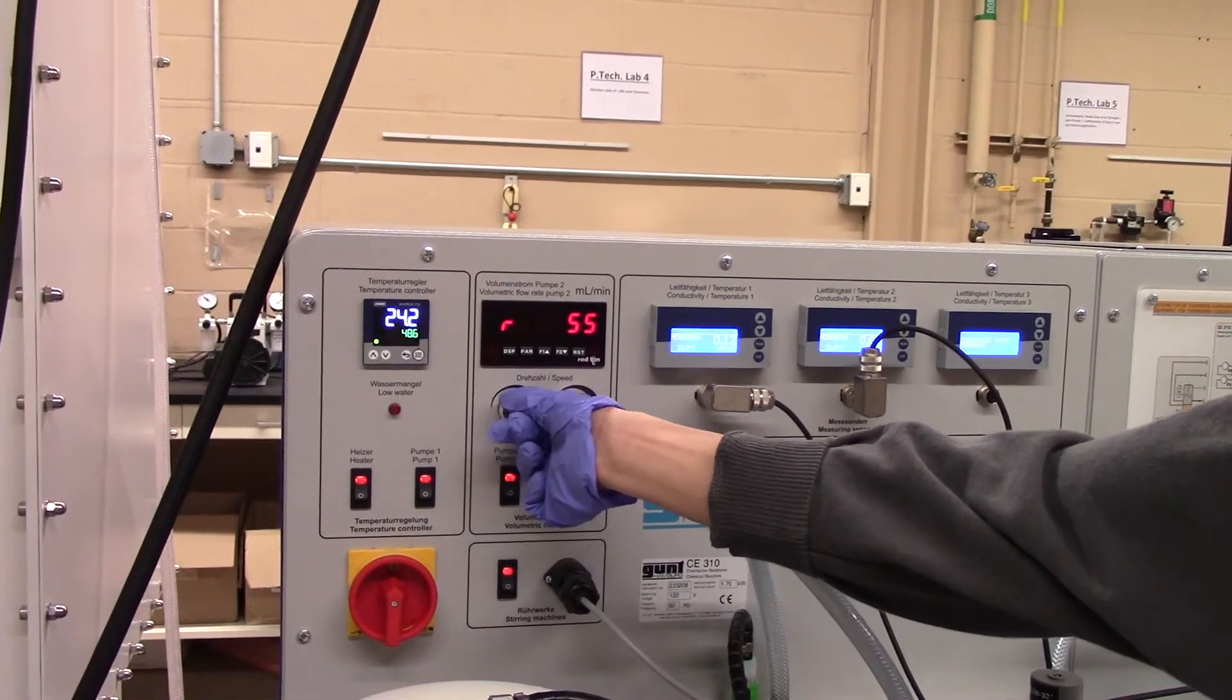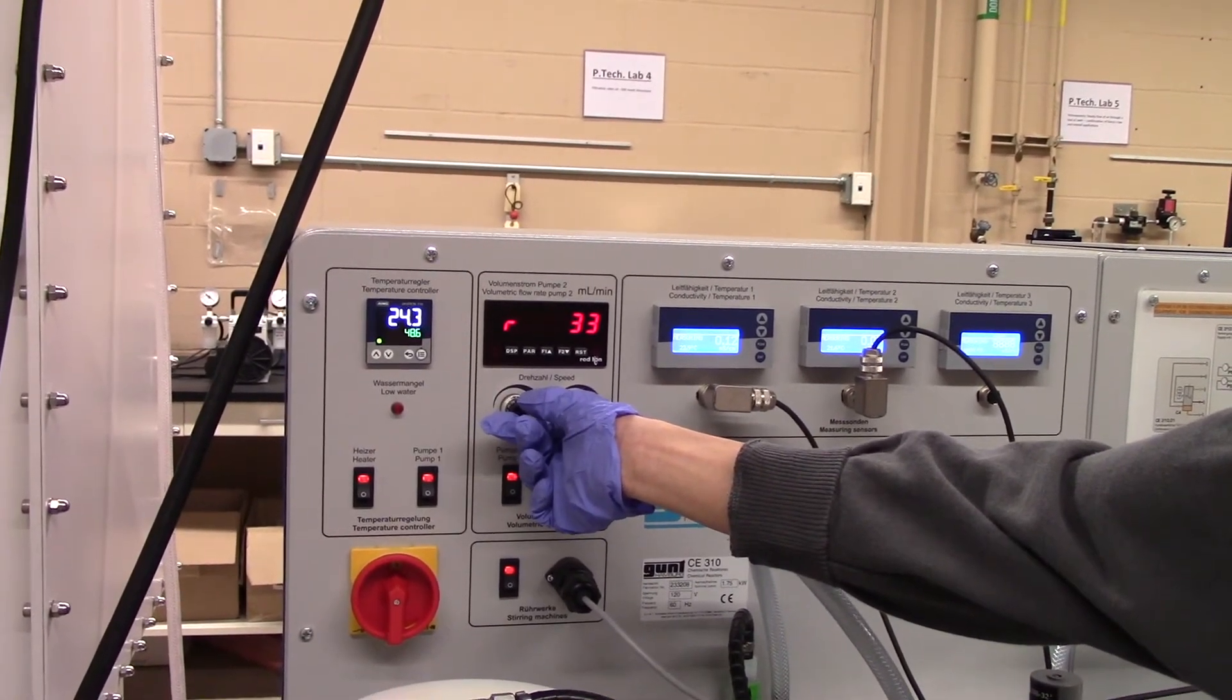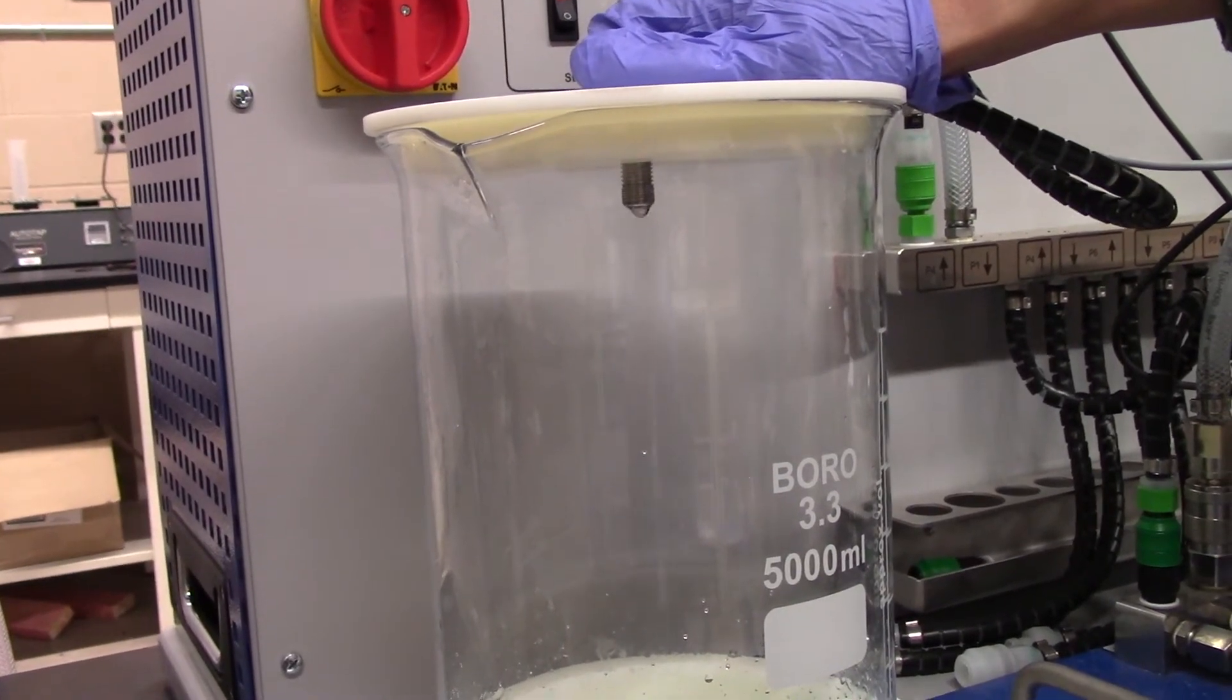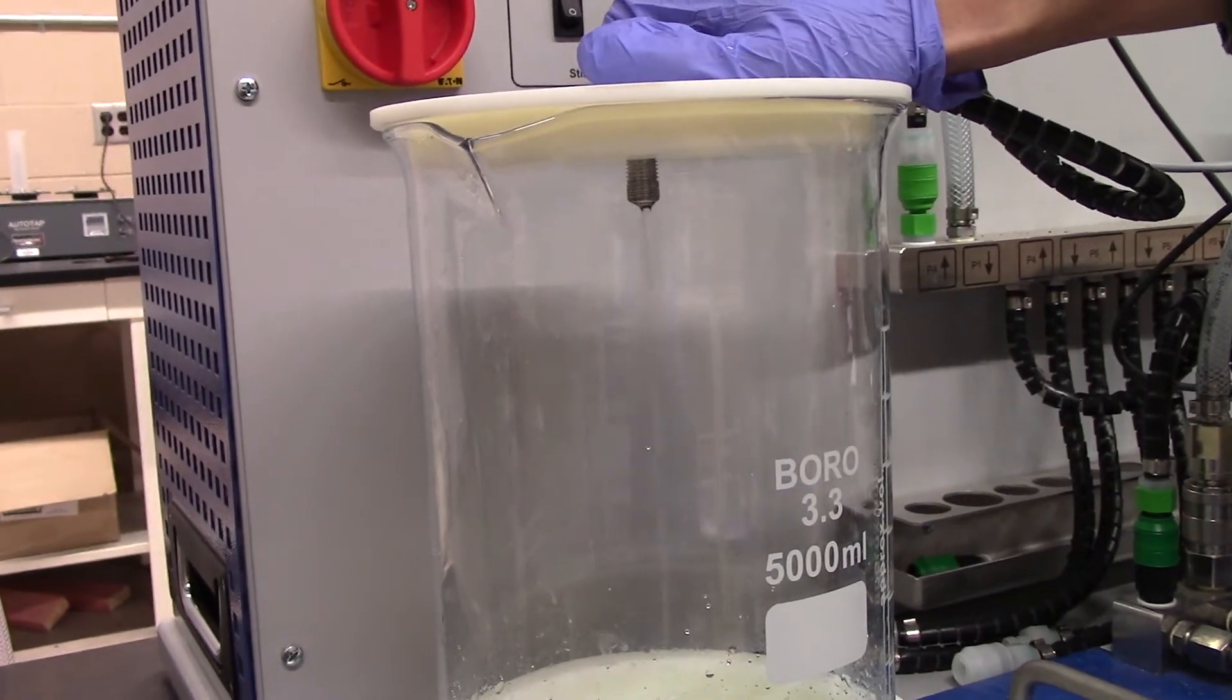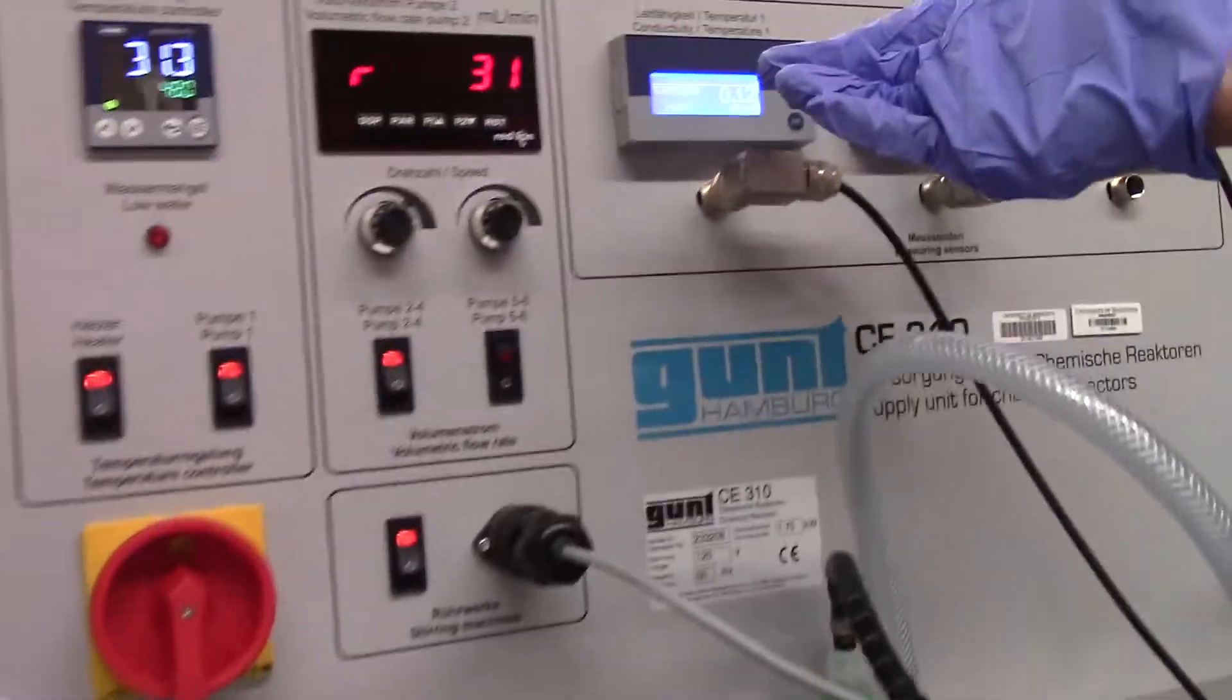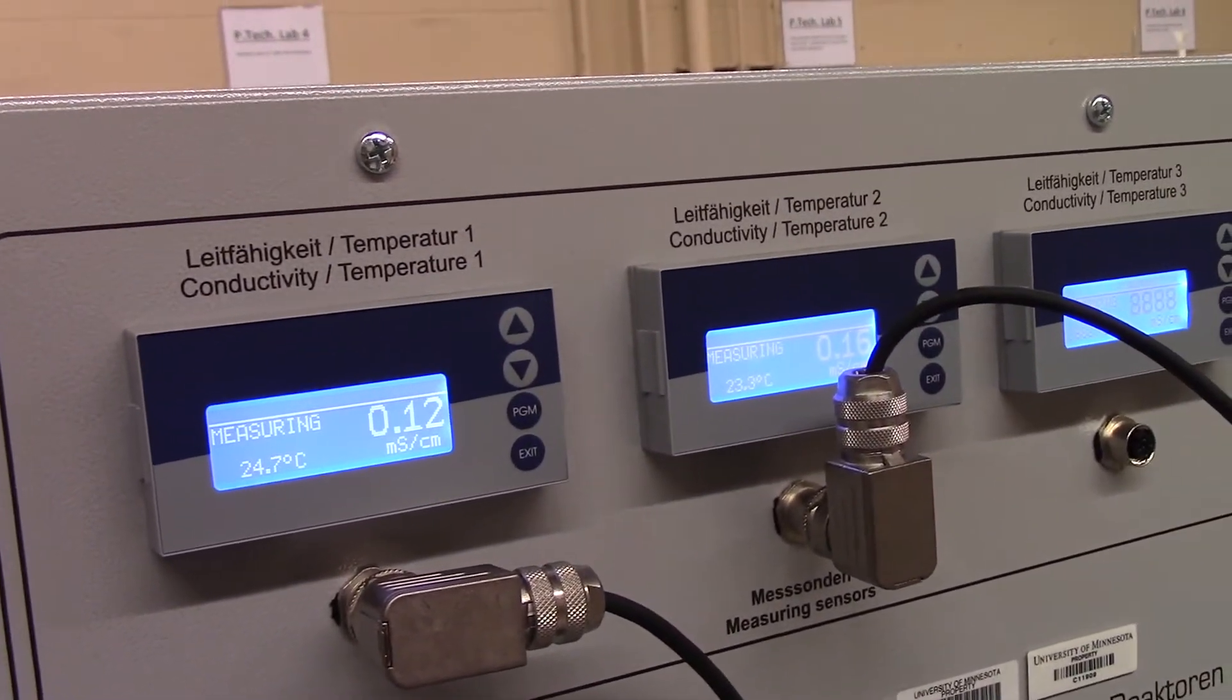Once this is complete, use the flow rate dial to set your desired flow rate, starting with 30 milliliters per minute. When you begin to see product flowing out of your product's tank, you must begin manually recording your conductivity, time, and temperature values in intervals of 2 to 5 minutes until your conductivity readings reach steady state.